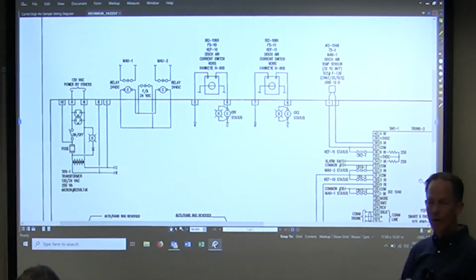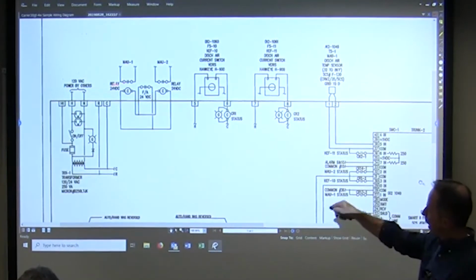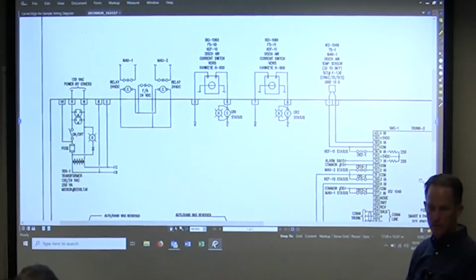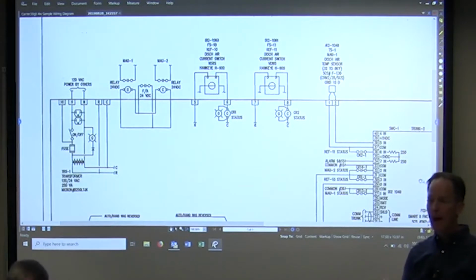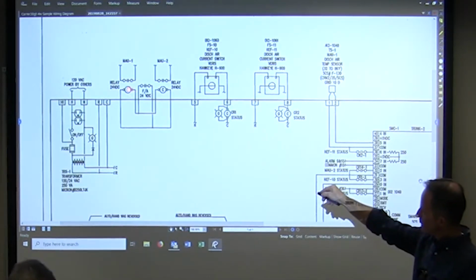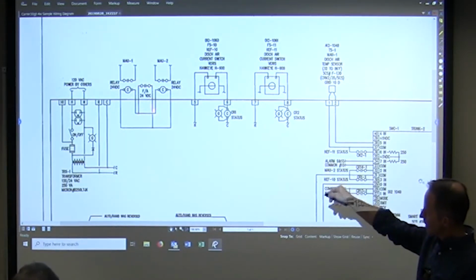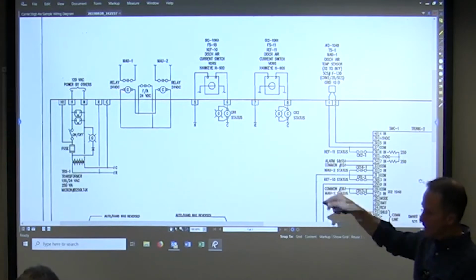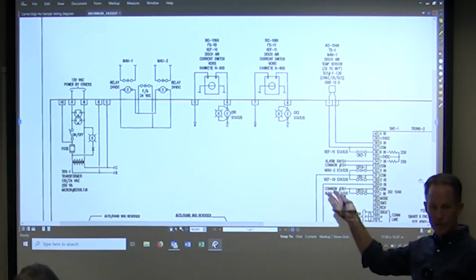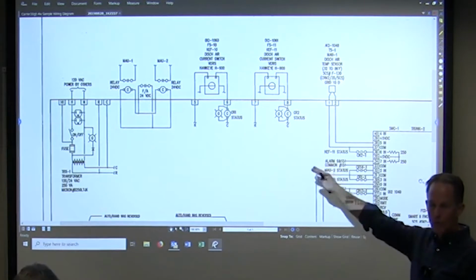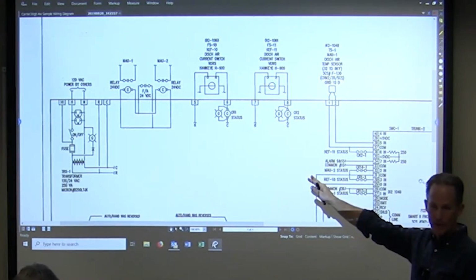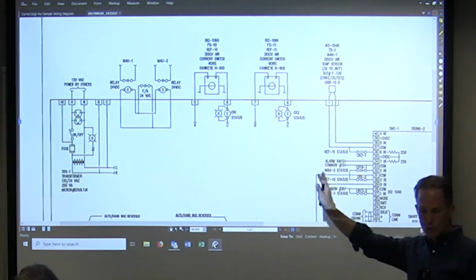Okay, and I know a few of you that are very familiar with relays see it. Does anybody else see why this won't work? There's no power going to the contact, the relay. Okay, so there's no power. If you follow this, say I start at this C, I come out, there's a dot right there, I go up through the contact, come down, there's a dot there, I come back around. There's nothing powering that circuit, it's just a circle. So as wired, nothing will happen, right? As drawn. Yeah, as drawn, and hopefully it's not wired that way, but if it is, it's not going to work.